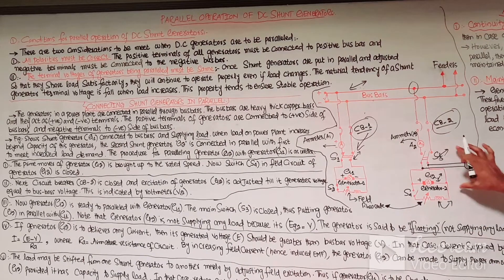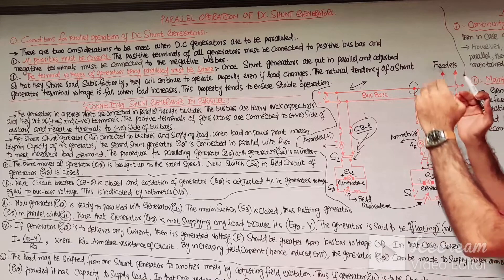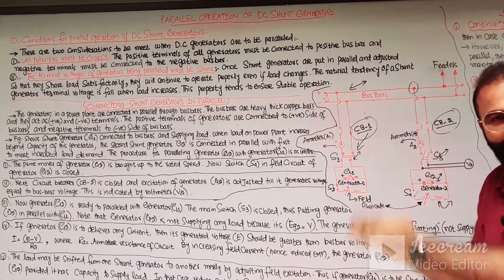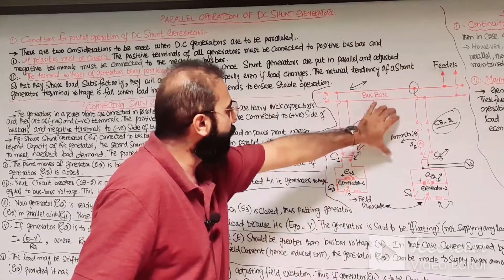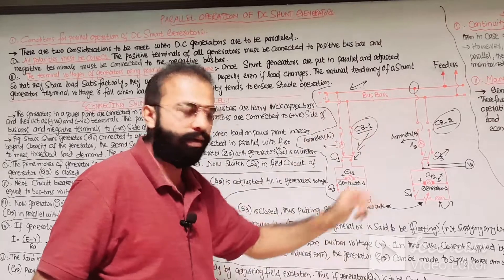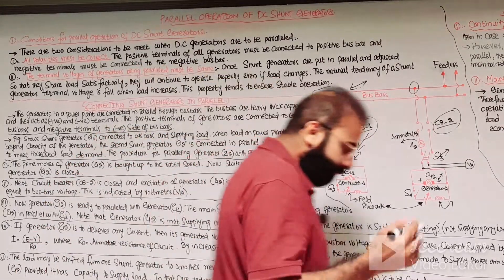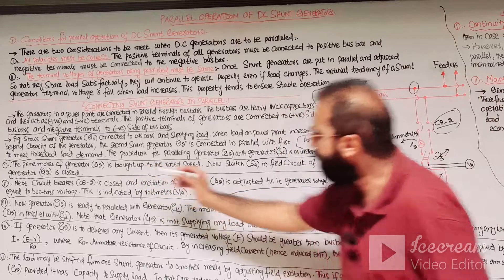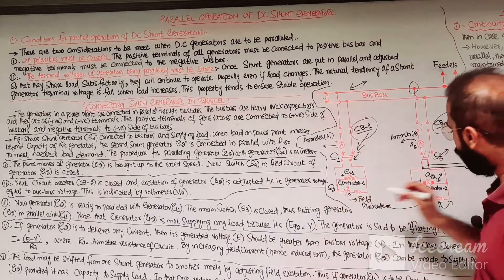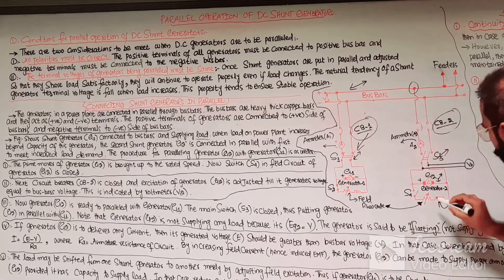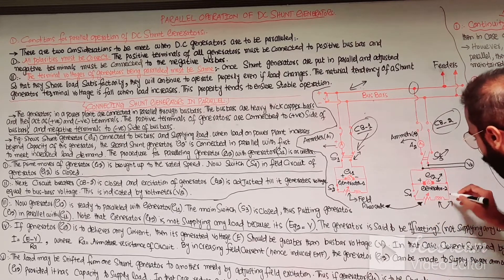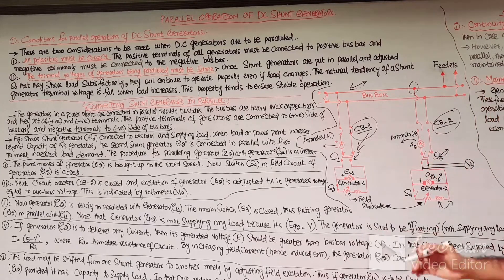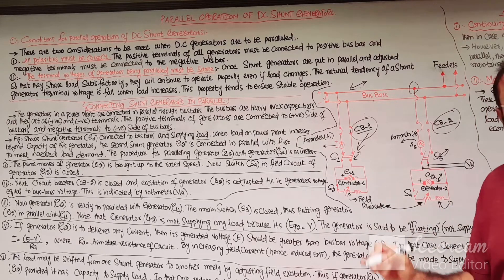The following steps describe how G2 generator is connected in parallel with G1. First, the prime mover of the G2 generator is brought up to the rated speed. Then switch S4 of the field circuit of the G2 generator is closed. This is the first step.